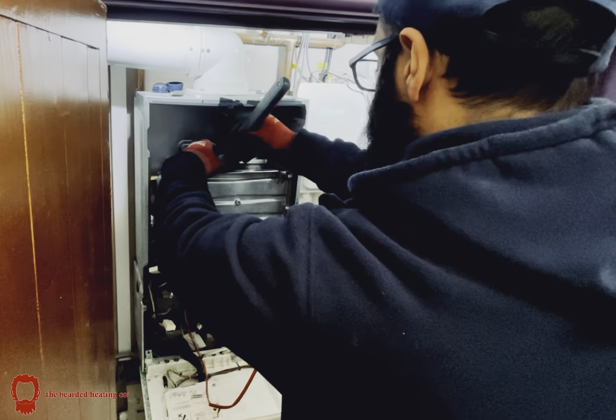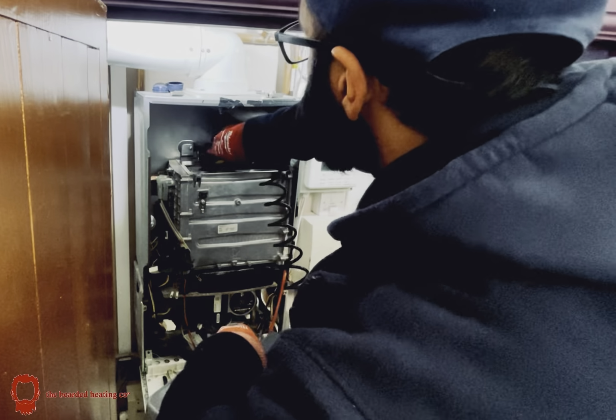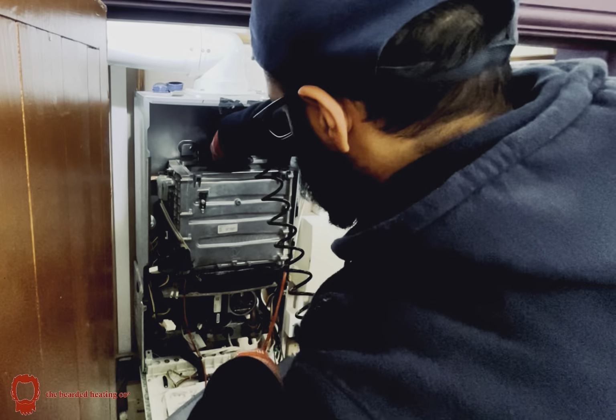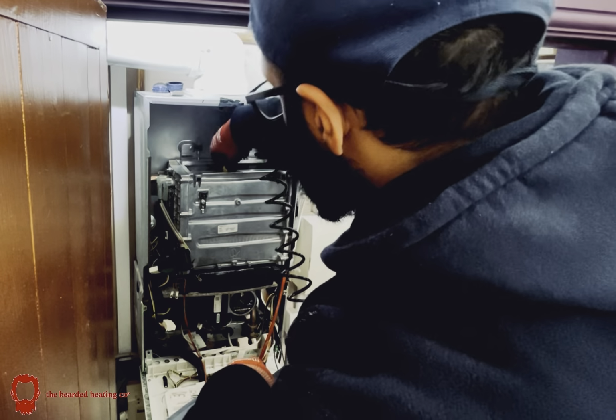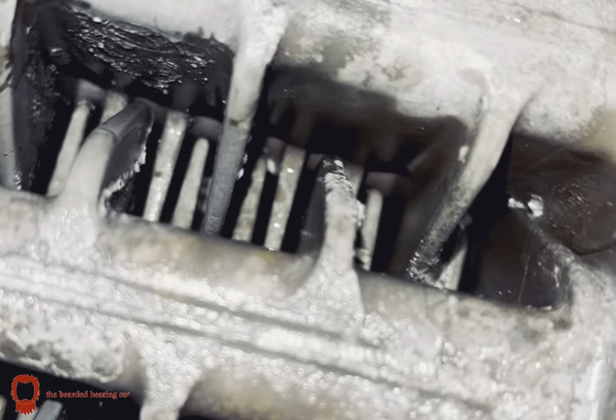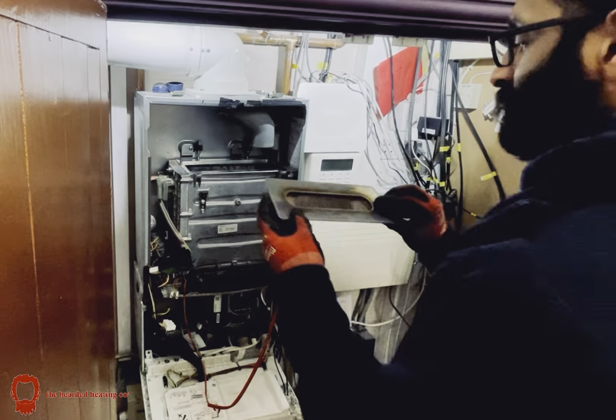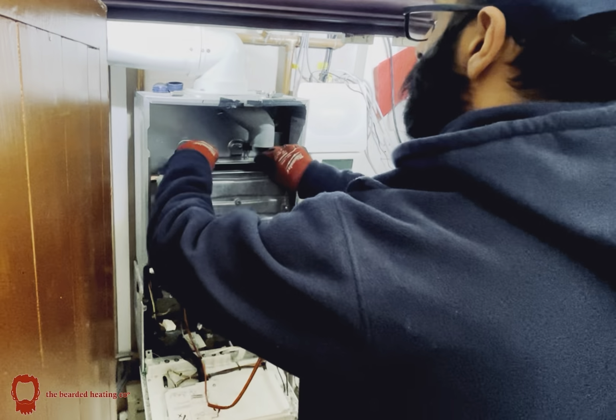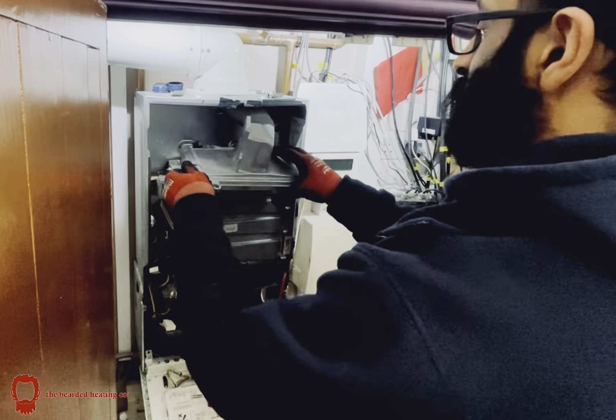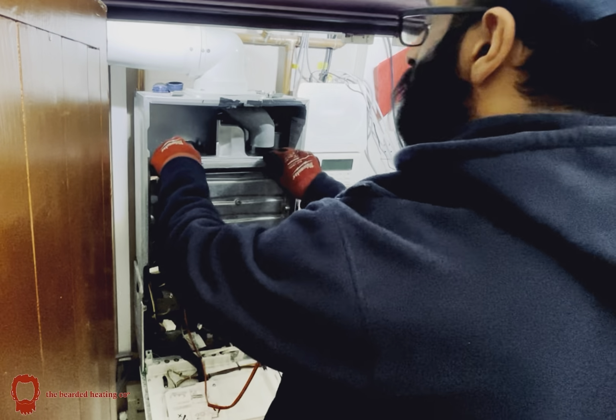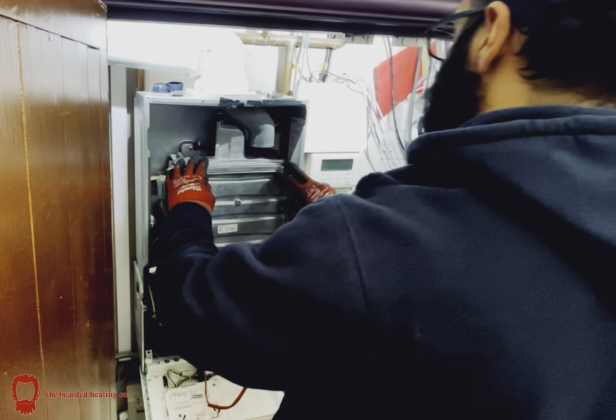This whole process took probably about 10 minutes. And now I'm washing it all out with my Karcher pressure washer. And there you go, that's your heat exchanger cleaned. Looking a lot better. Put the burner back in the same way you found it. Make sure you replace any seals, especially the burner one. I've just replaced that.